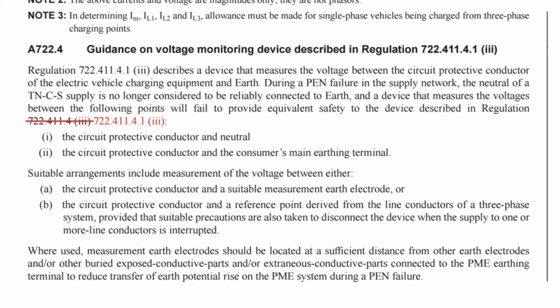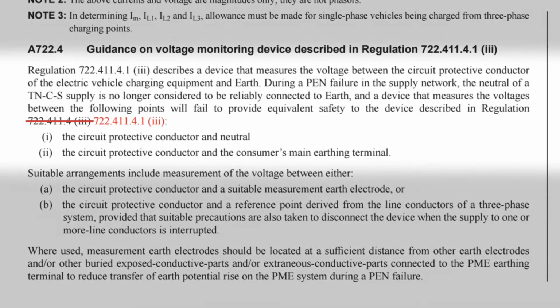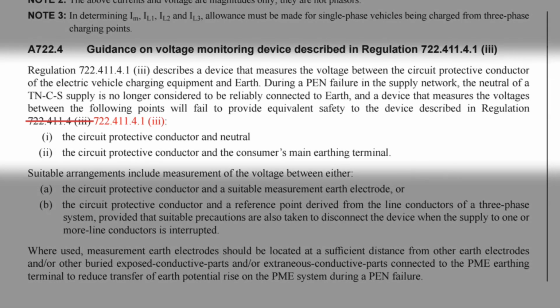I'll read this from the corrigendum as there was a slight mistake in the original. Now bear in mind when we read PEN fault in this paragraph, we're talking about the loss of that combined neutral and earth conductor. Regulation 722.411.4.1 indent 3 describes a device that measures the voltage between the circuit protective conductor of the electric vehicle charging equipment and earth.